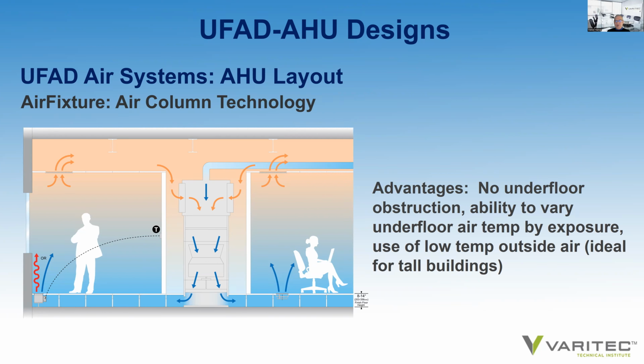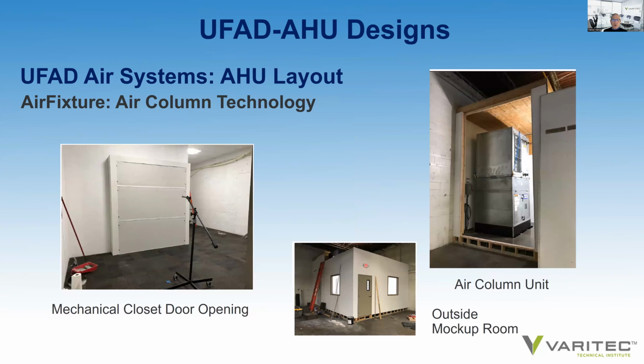This is a graphic that shows the elevation of an installed air column solution. As you can see, the air is injected directly to the plenum, and duct would be assigned depending on what is necessary to cover the square footage of UFAD plenum to be covered. But this design concept allows for the 8-inch, the 10-inch, 12-inch plenum height considerations that offer a lot of advantages and cost savings to building owners.